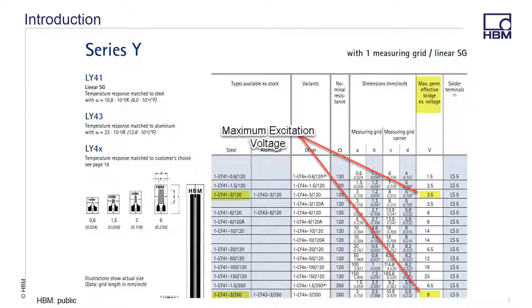Looking at our strain gauge catalog, you will see a lot of information on the specifications of each gauge. We provide information on the orientation, the dimension of the package, the resistance, grid size, etc. One of the specifications that is overlooked and is not well understood is the maximum permissible bridge excitation voltage. In this video, we will explain this and describe how it is calculated and what you need to consider when applying excitation voltage to your gauges.